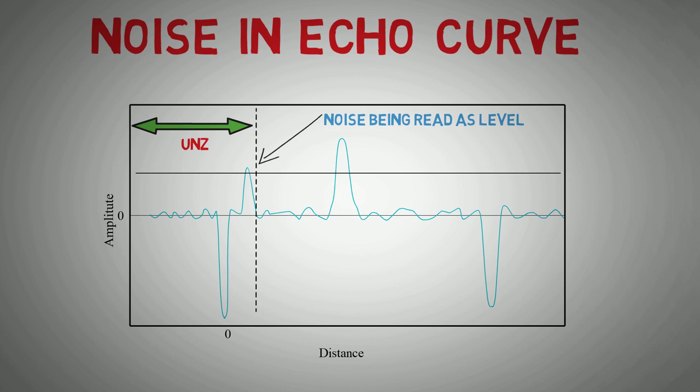If you see a similar echo curve with noise near the top of the probe in a transmitter that has previously been healthy, then it's not always caused by the vessel. This can be caused by product condensation building up at the top of the probe, causing the unwanted reflections and false level readings. I've seen this in gas condensate systems where the reading will suddenly shoot up to 100% level.